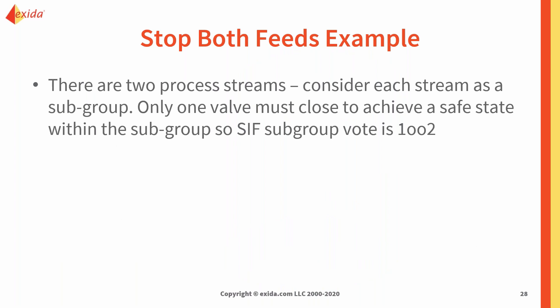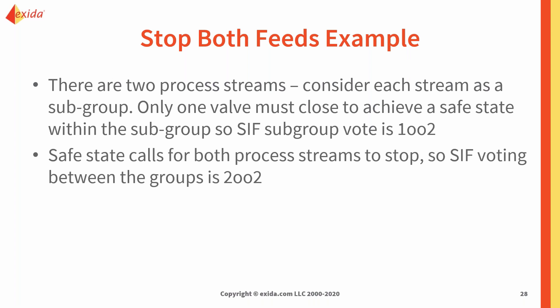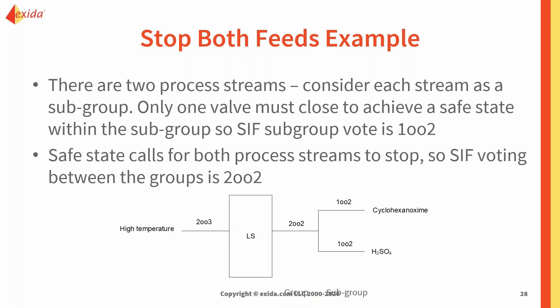We have two process streams, each called a subgroup, decided based on the physical two different flows. We've got two valves in each subgroup, so we can do one out of two voting within the subgroup. Because we have two subgroups, the overall voting between those groups is two out of two — both have to be successful to achieve the safe state. On a logic diagram, you can see clearly the cyclohexanoxime line and the sulfuric acid line, each with one out of two voting, and we need both lines successful.